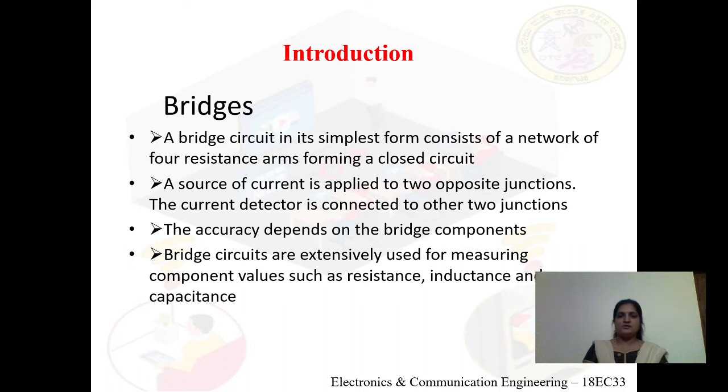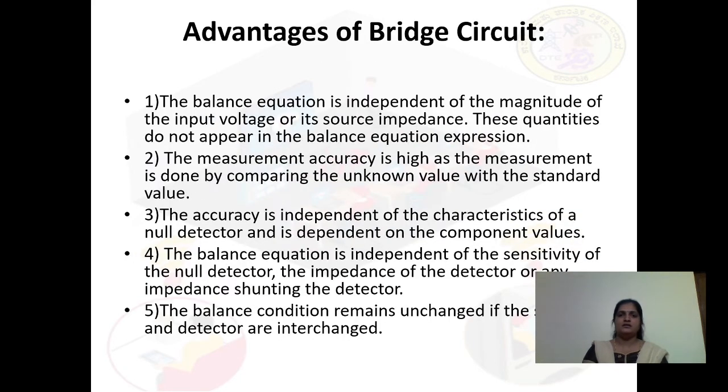And finally, these bridge circuits are extensively used for the measurement of components like resistance, inductance and capacitance. Coming to the advantages of a bridge circuit, the balance equation is independent of the magnitude of the input voltage or its source impedance. These quantities do not appear in the balance equation expression. That is one main advantage, so it's independent of magnitude while balancing the bridge.